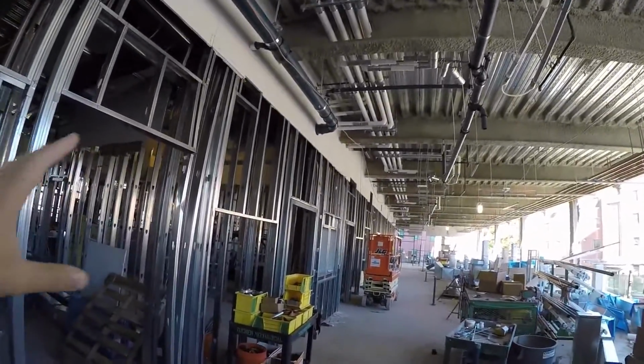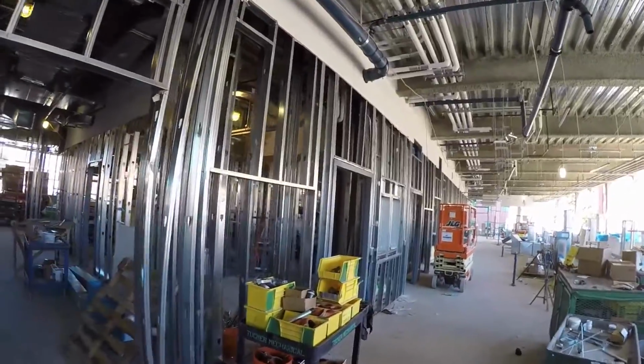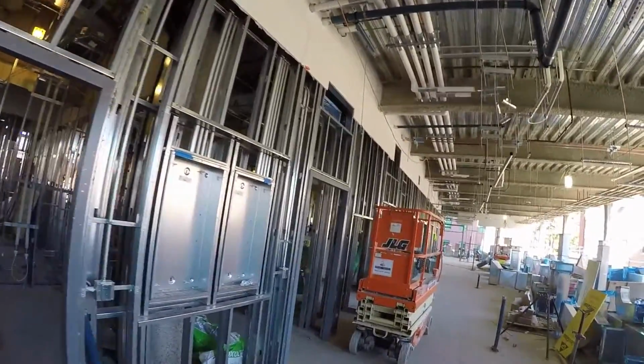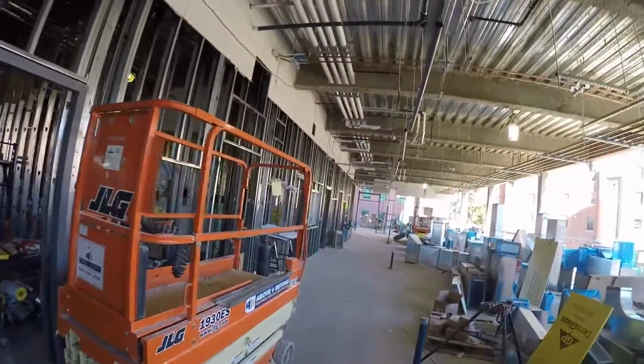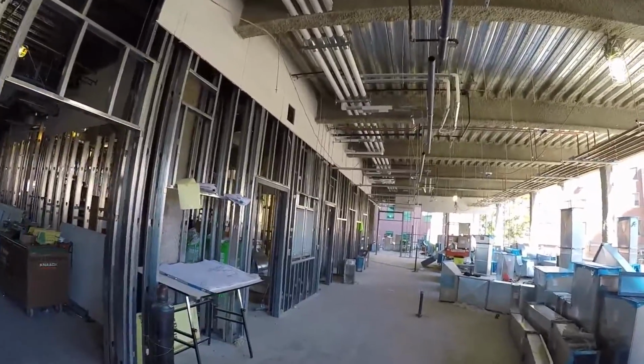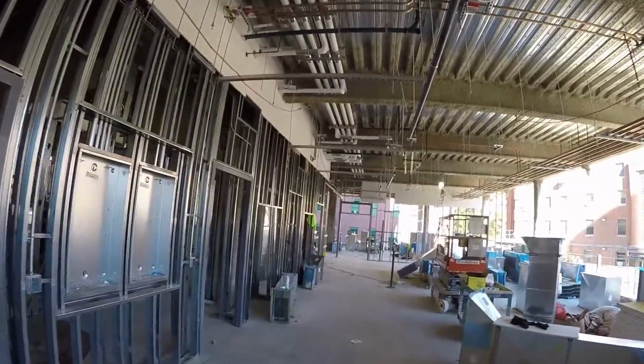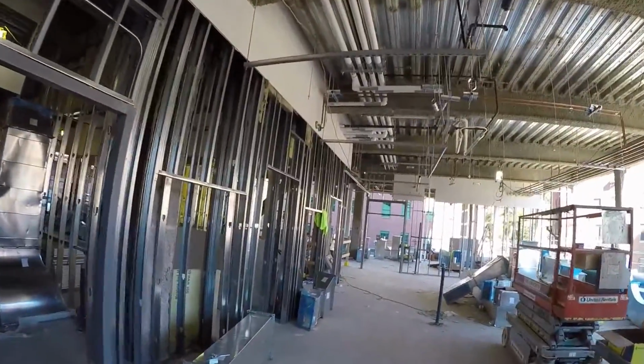In the center between the labs on the south and on the north is all of the service areas in through here. Then there's 2 areas where the ductwork rises. One is next to the bathrooms on the west, and one is on the east. For the massive amounts of ductwork that come up here, all of the fume hoods have ductwork, all the fresh air. And when you have fume hoods, well, the air that comes in and comes out has to be controlled also to balance the space. So the air that the fume hoods take out, it's made up with fresh air.